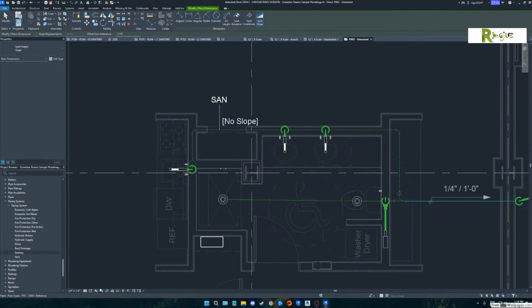So now I'm saying, does this? There you go. See, some of the stuff they sloped, but some they didn't. The main line they sloped, but the trunk or the branch lines they did not. That requires 2 clicks. And you see they didn't even slope it from there to there, which would be a problem if you're trying to do coordination.